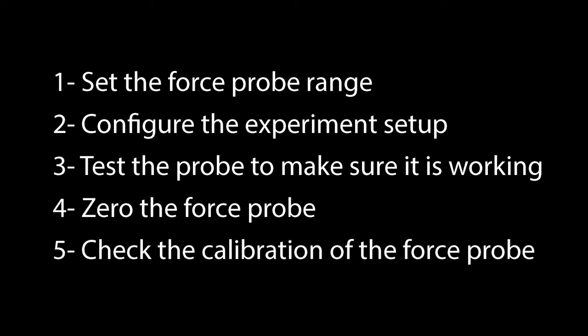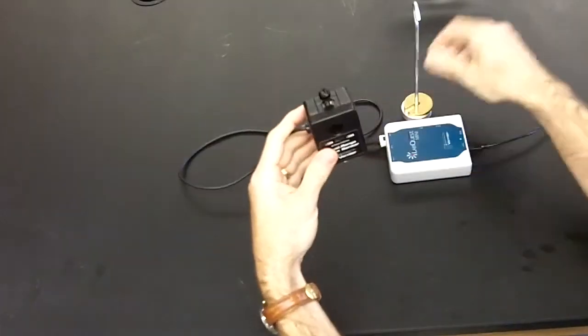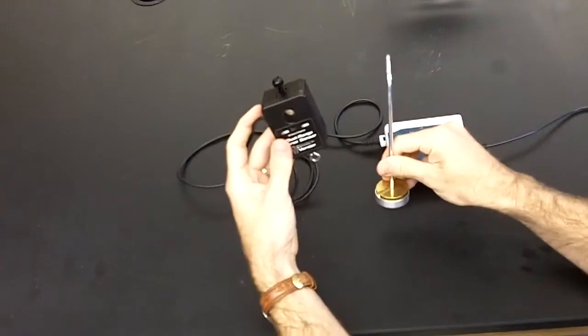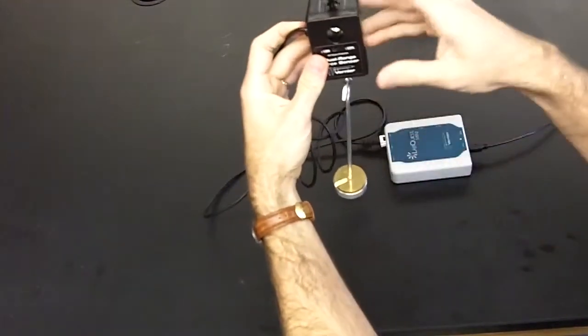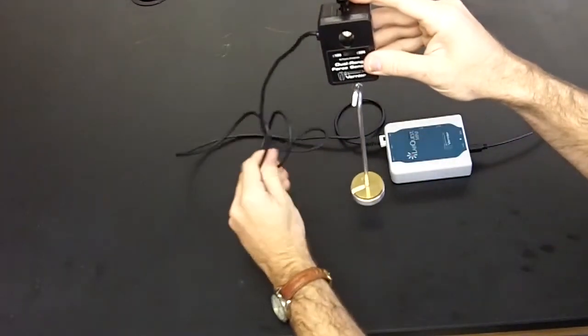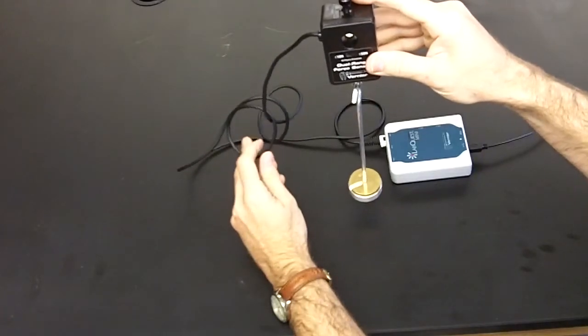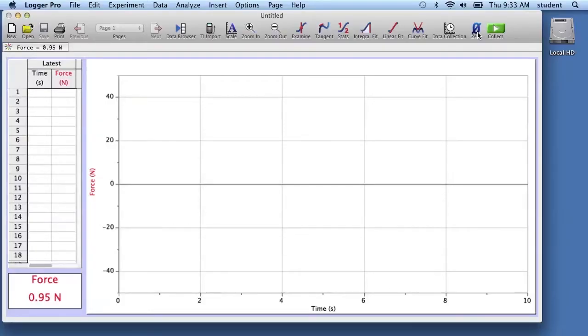And 5. We always check the calibration of any new measurement tool to make sure that the measurement accuracy of the tool is as expected. For the force probe, this can be done by applying a known force to the probe. In this case, we hang a 100-gram mass from the probe. This applies a force of 0.98 newtons. We note that the probe reads slightly different than the expected value. We can use this calibration point, then, to correct any force readings.